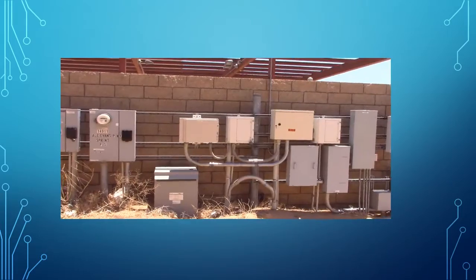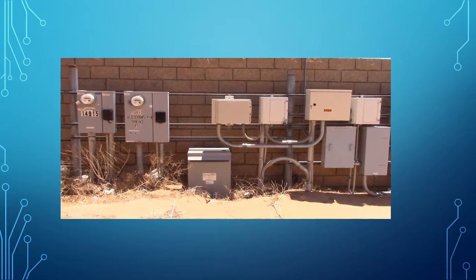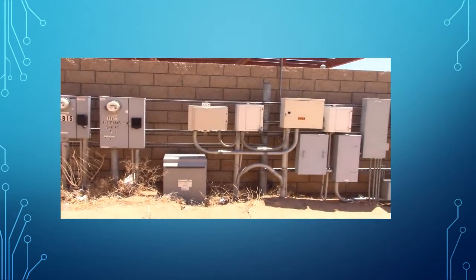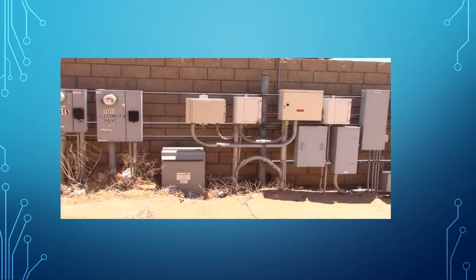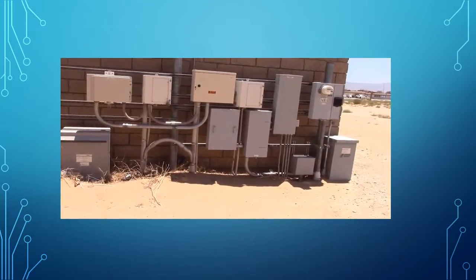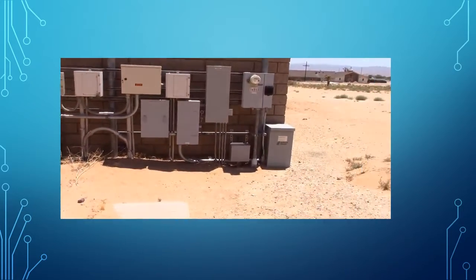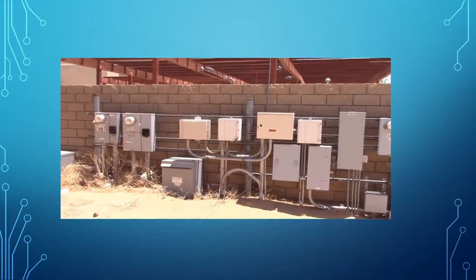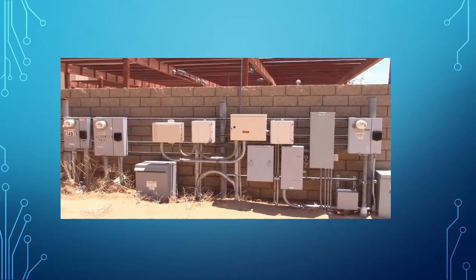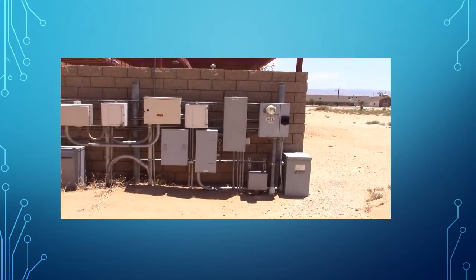So what we're going to do is take this temperature, and add 11 degrees because it was 99 right now at the heat of the day. It was 110 2 days ago, which is what the transformers experienced. So whatever the thermometer says, we add 11 degrees to it. Then we're going to look up a Celsius Fahrenheit comparison chart, and compare to see how much heat these transformers have been exposed to, to show you what they've been put through because of improper management, maintenance, and installation.